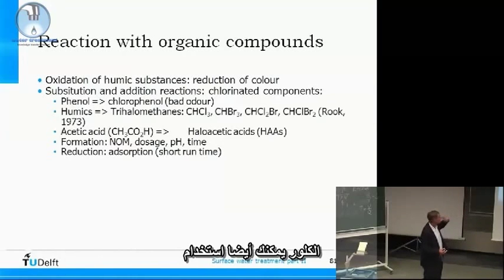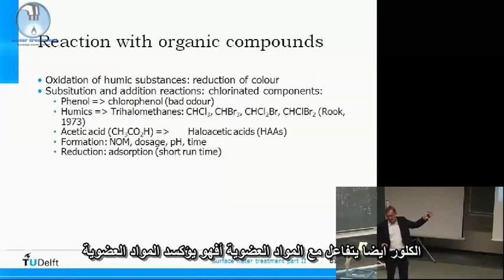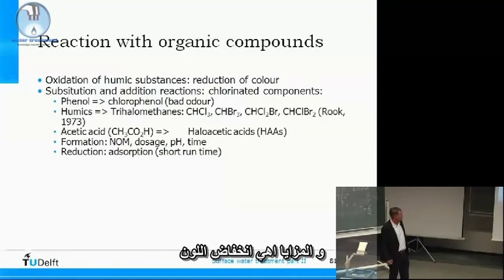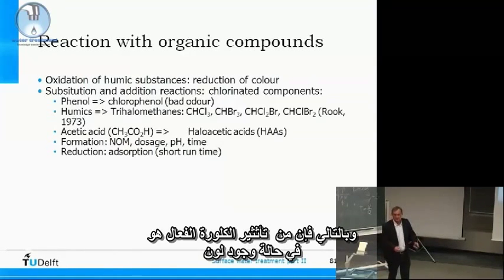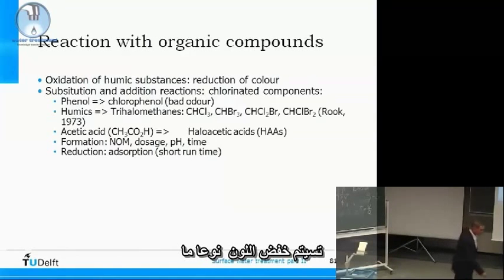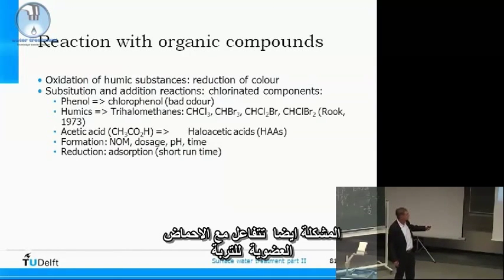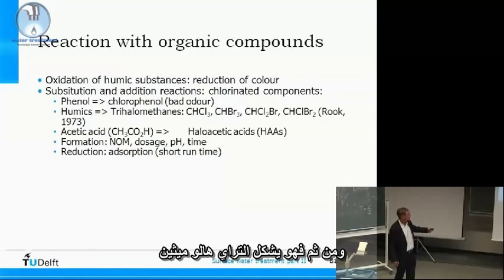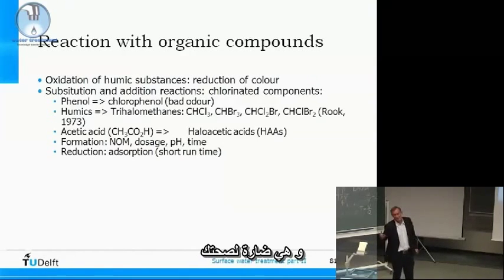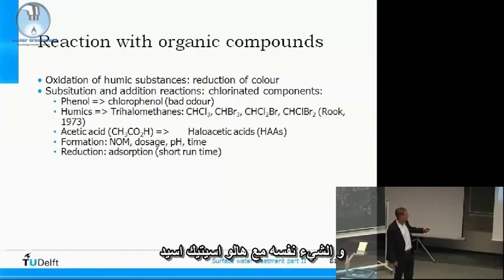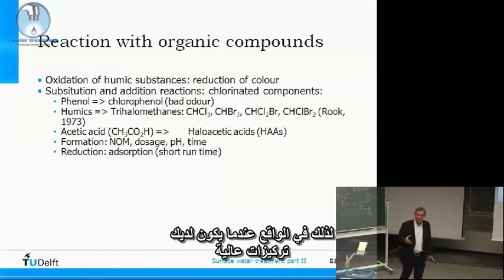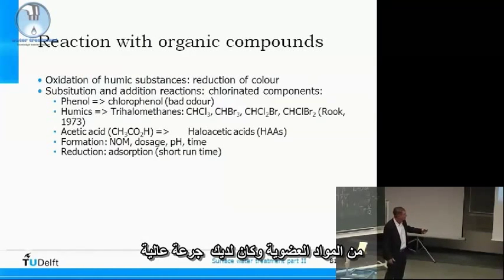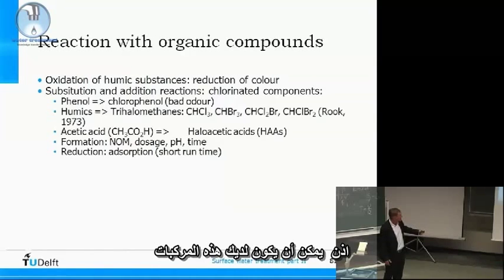Chlorine can also react with organic matter — it oxidizes it. The advantage is that color is reduced, so when you have high color, it is slightly reduced after chlorination. But the problem is that chlorine reacts with humic acids and forms trihalomethanes, which are bad for health. The same applies to haloacetic acids. When you have high concentrations of organic matter and high dosages, this formation can occur.